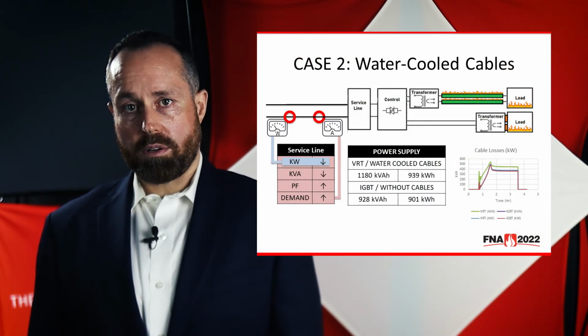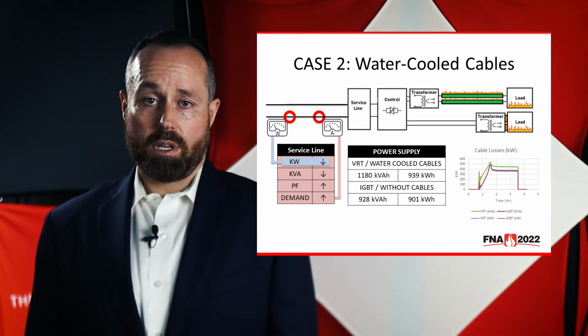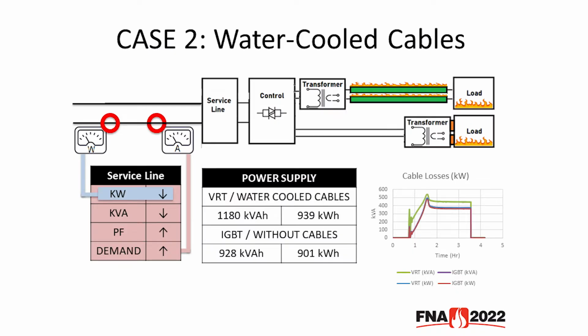If we go back to the standard model and replace the water-cooled cable with a closely coupled IGBT MFDC power supply, a clear electrical benefit can be seen. The pictorial schematic above shows the closely coupled transformer shrinks the secondary circuit and reduces the unnecessary losses outside of the hot zone. This close coupling makes the impedance triangle smaller and results in lower kW demand, lower kVA demand, better power factor, and lower peak current demand. Specifically for this run, the total kVA hours was reduced from 1180 to 928, a 21% reduction, and the total kW hours was reduced from 939 to 901, a 4% reduction.